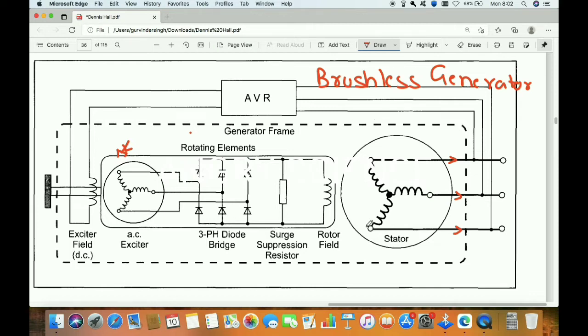This whole part is the stator — it is the stationary part and it has three windings. This winding is stationary and not rotating. When a conductor cuts a field, an EMF is produced. Here the conductor is stationary but the field is moving. We need relative motion between them — if the field moves or the conductor moves, it is fine. Here we rotate the field, which is cut by the conductor, and hence the EMF is produced.